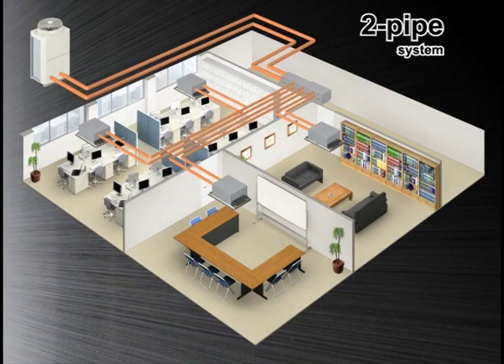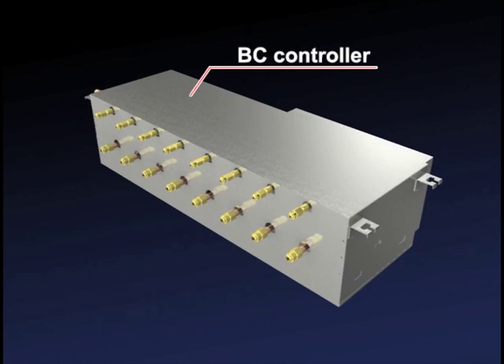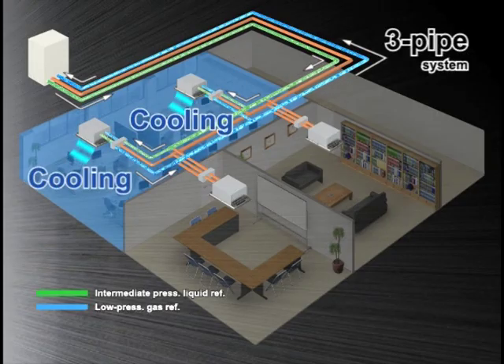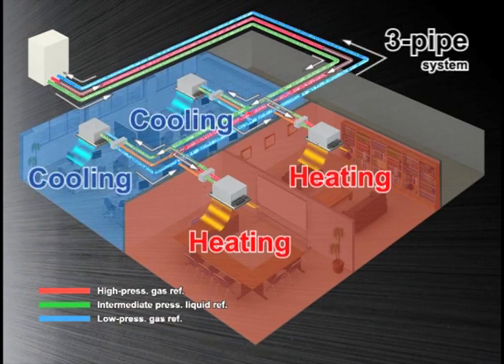The key to our City Multi Heat Recovery System lies in the BC controller. Three-pipe systems require three refrigerant pipes: one for liquid refrigerant and another for low-pressure return refrigerant, both for the cooling operation, and the third one for gas refrigerant for the heating operation.